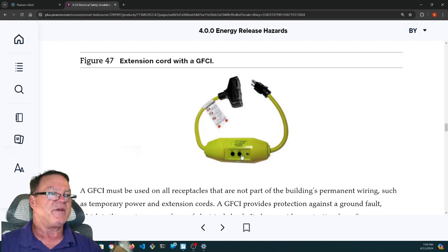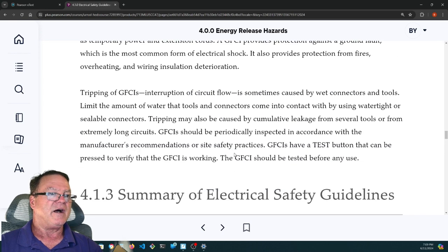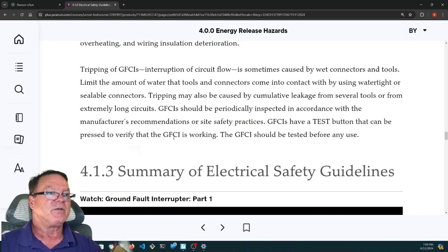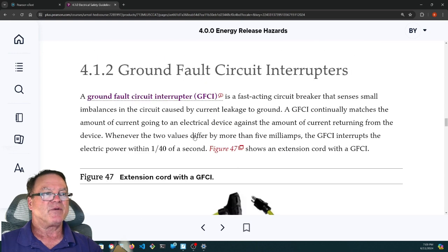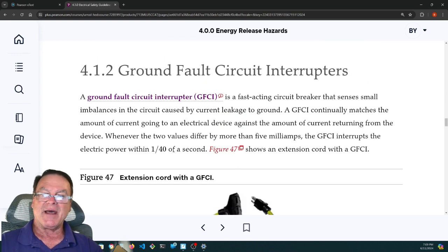Here's a GFCI pigtail. You've got test and reset, just like the GFCI in your bathroom. Basically what this GFCI does is exactly what they were talking about. It measures the amount of current in both the hot and the neutral. And if the two are the same, the GFCI is happy.